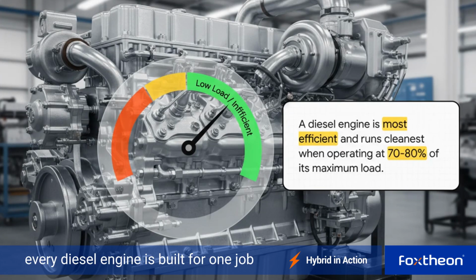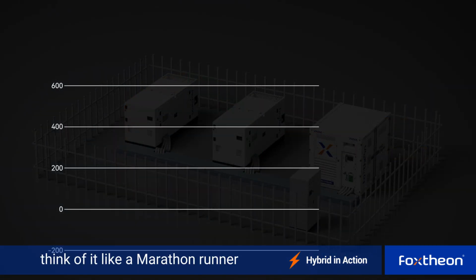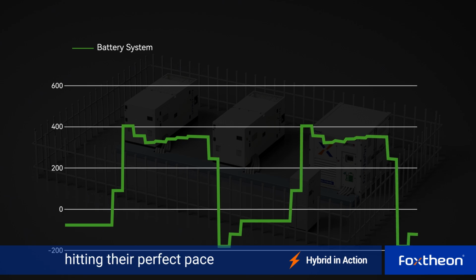Every diesel engine is built for one job: to run hard and run consistently. This is its sweet spot, that perfect range between 70 and 80 percent of its max load. When it's in that zone, it's at peak fuel efficiency and running clean. Think of it like a marathon runner hitting their perfect pace.